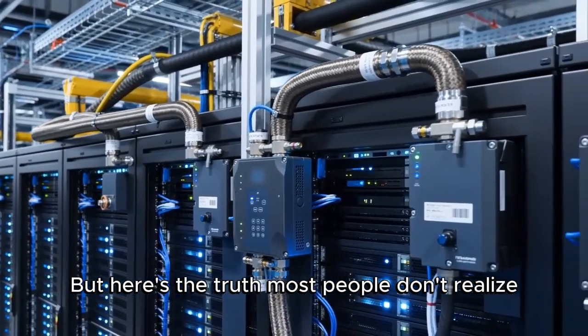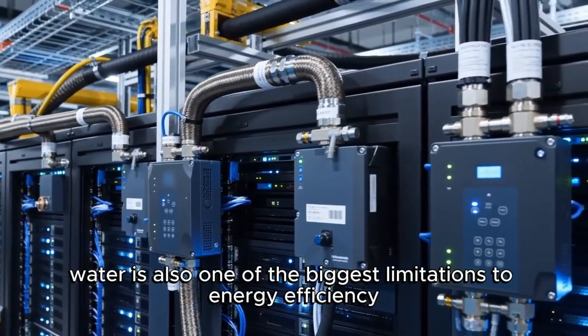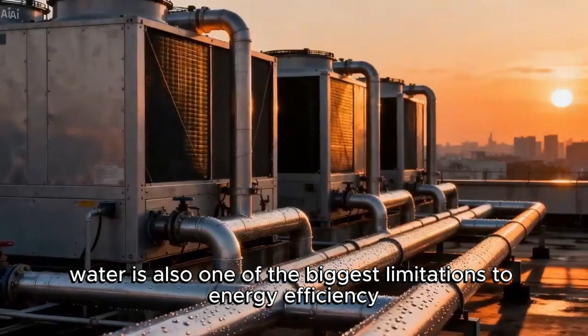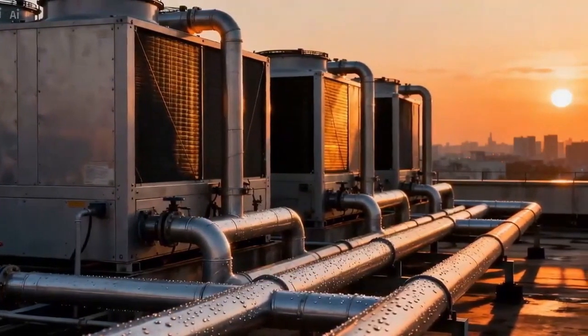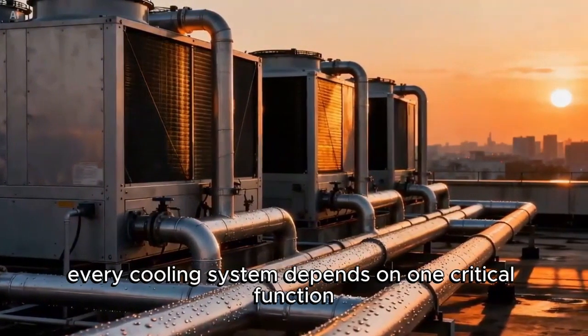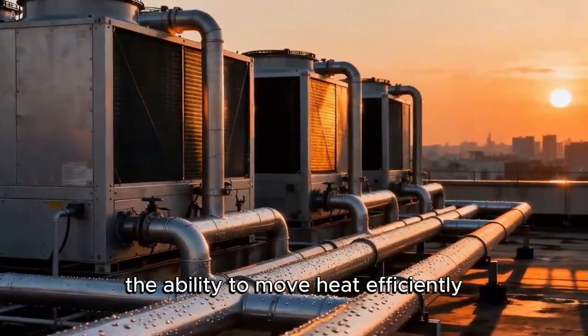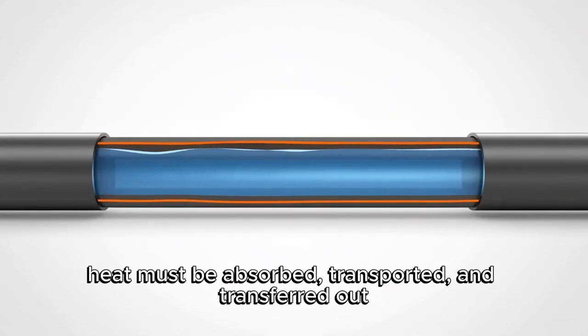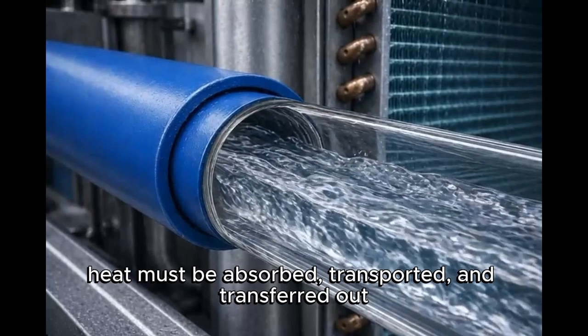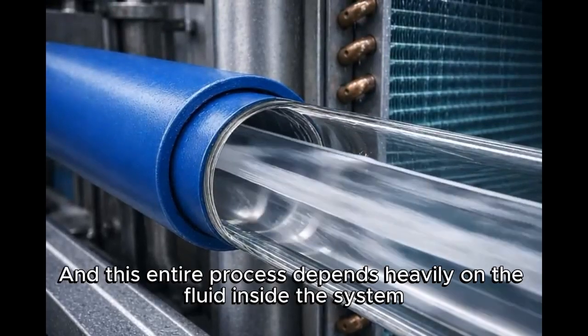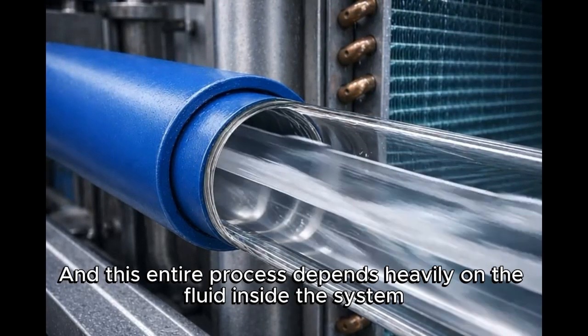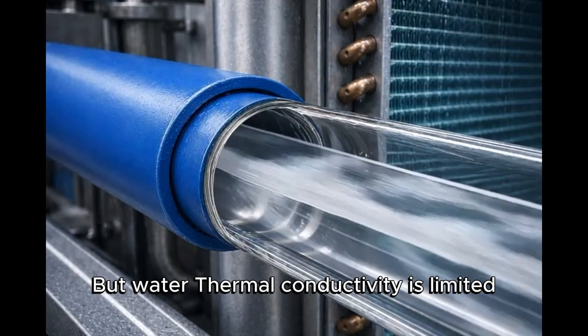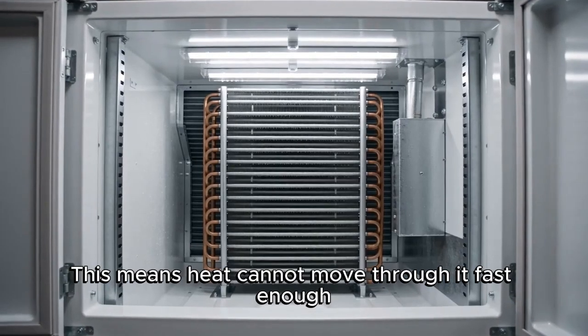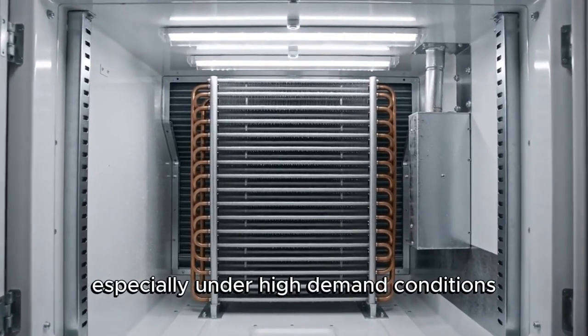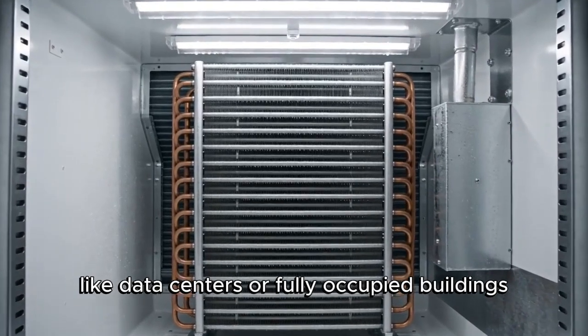But here's the truth most people don't realize. Water is also one of the biggest limitations to energy efficiency in modern cooling systems. Every cooling system depends on one critical function: the ability to move heat efficiently. Heat must be absorbed, transported, and transferred out. And this entire process depends heavily on the fluid inside the system. But water thermal conductivity is limited. This means heat cannot move through it fast enough, especially under high-demand conditions like data centers or fully occupied buildings.